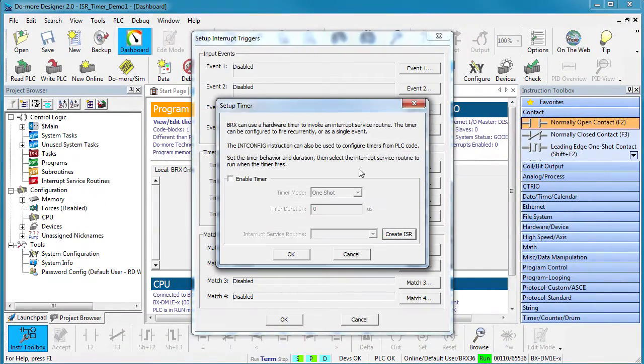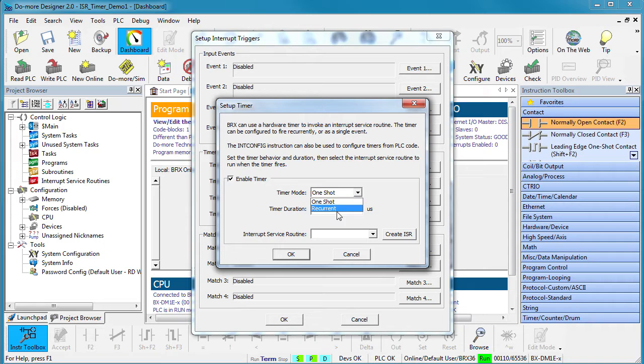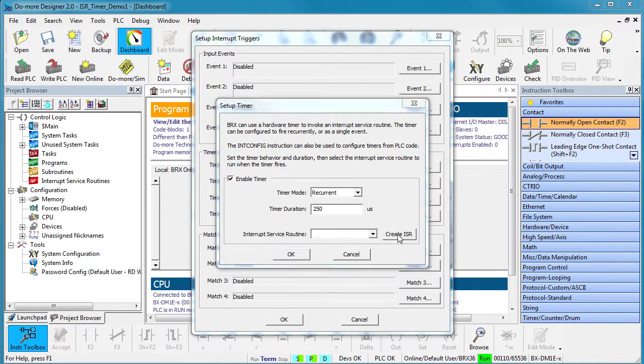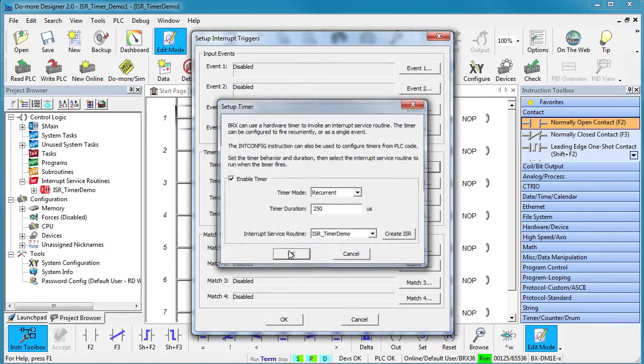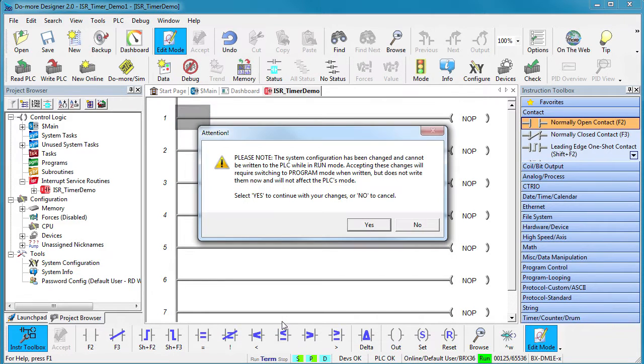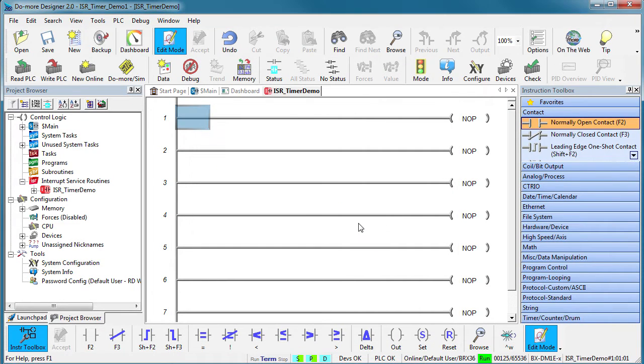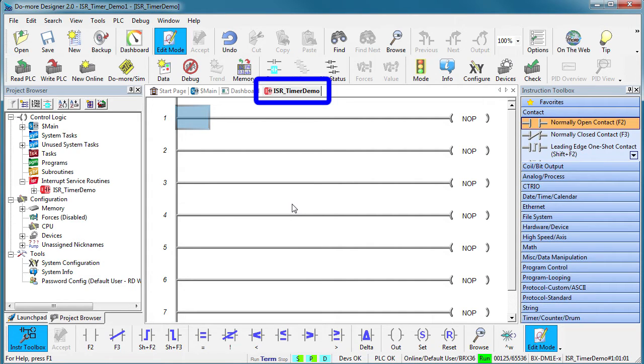Let's set up a timed interrupt, make it recurring with a duration of 250 microseconds, and create a new ISR to handle that timer-generated interrupt event. So now, every 250 microseconds, regardless of the scan time, this ISR will be executed.